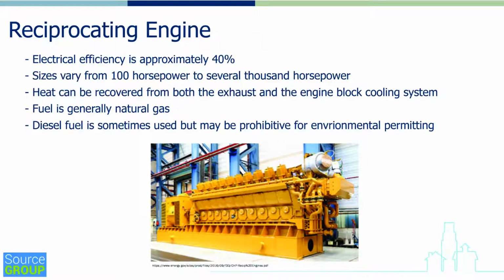Heat can be recovered from the exhaust of the engine and also from the cooling system that cools the engine block. However, the exhaust temperature is generally much higher than that of the cooling water. The cooling water has a temperature somewhere in the range of probably 180 degrees. So that can be used to generate domestic hot water in cases of buildings where they're close, and 180 degrees can be used sometimes to heat the building. However, to drive an absorption chiller, 180 degrees is probably not sufficient temperature.